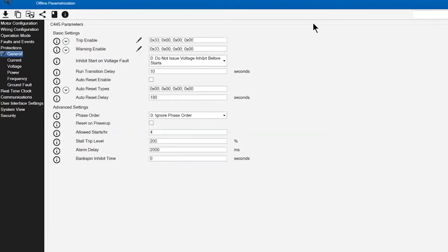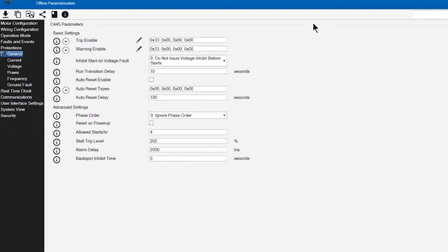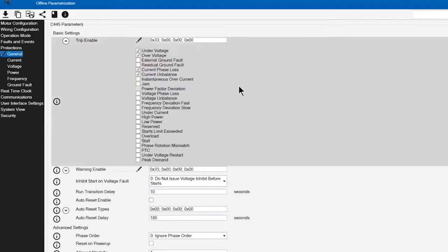From this page it allows us to enable different types of protective functions that would either result in a trip or shutdown of the motor circuit or generate a warning that could be a visual or a message transmitted to a PLC. I'm going to walk through those and set up a couple of critical protections.